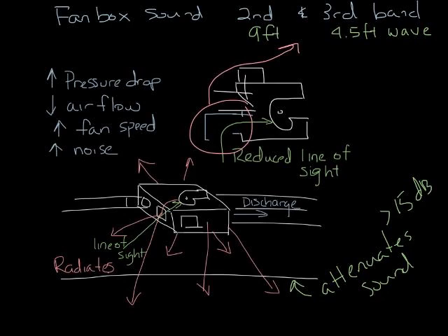You can do this in the team selection software. When installing VAV boxes, you should mount them as high as possible above the ceiling. If you're within a couple of inches of the ceiling, it won't give you the attenuation you expect. Another thing we often see is oversizing VAV boxes in hopes of making it quieter.